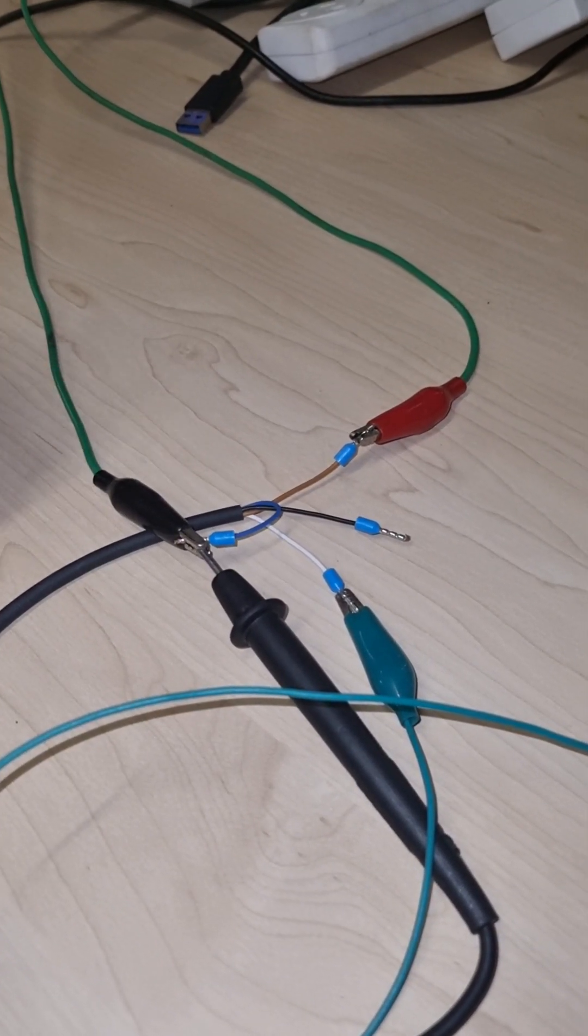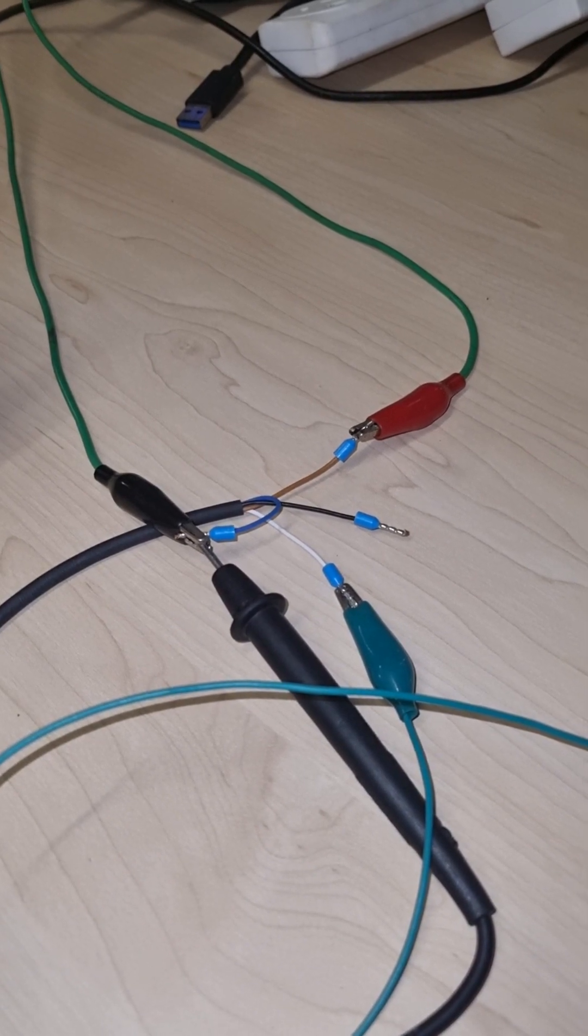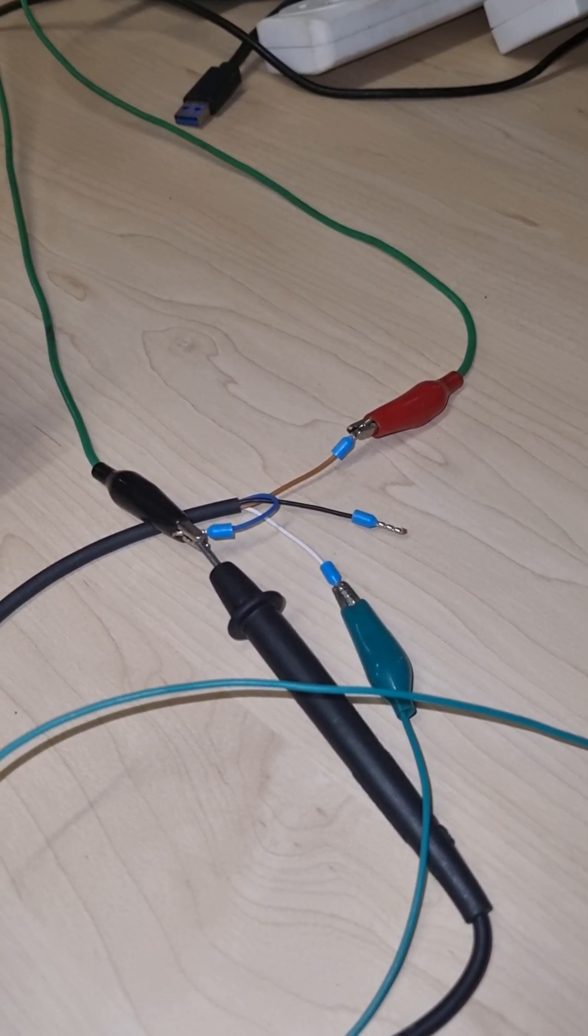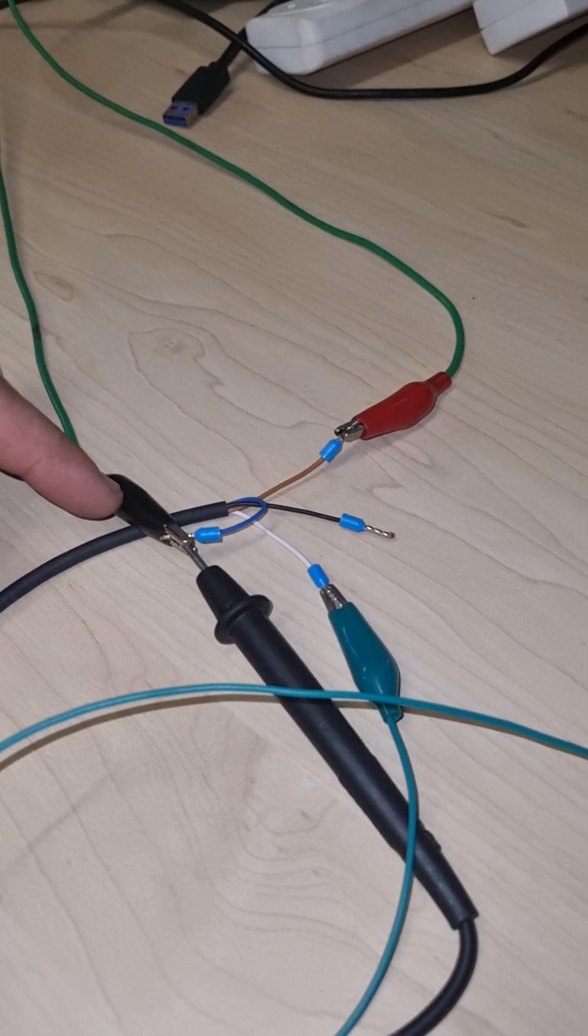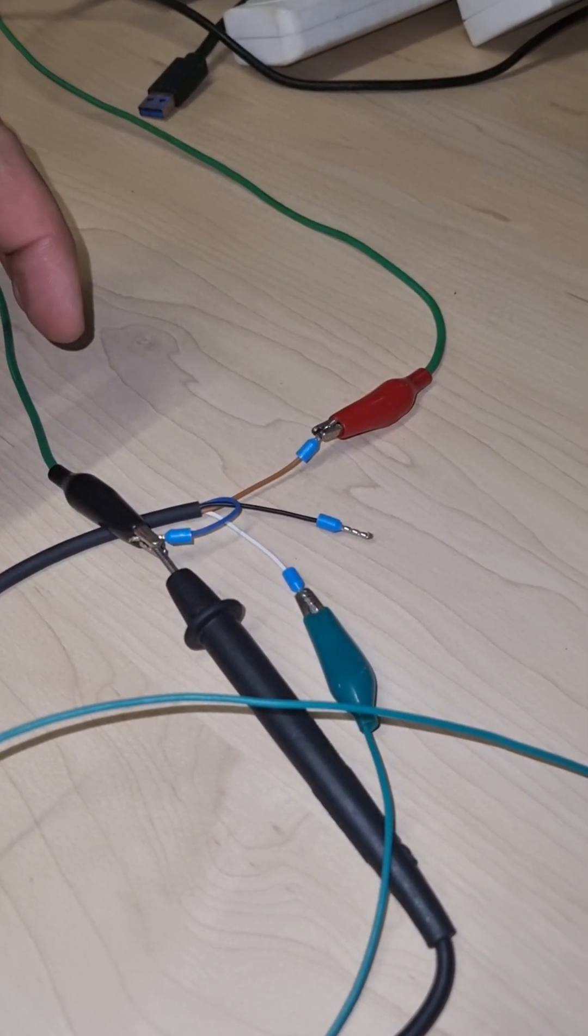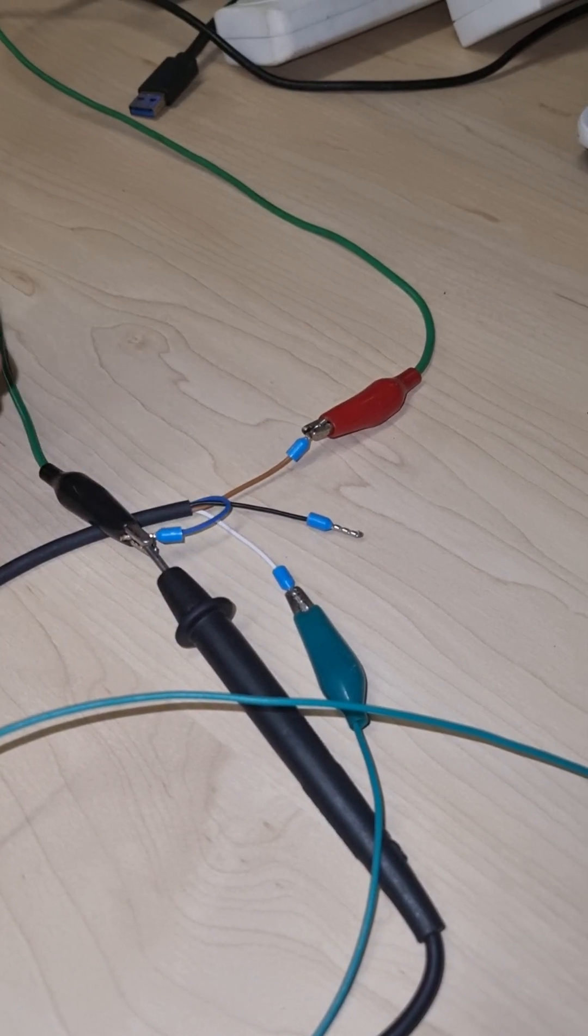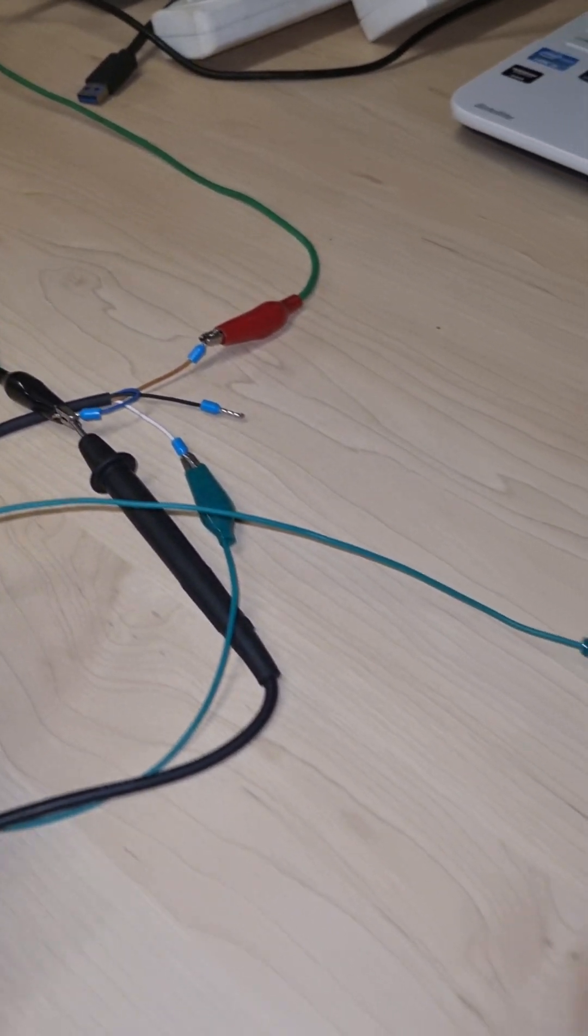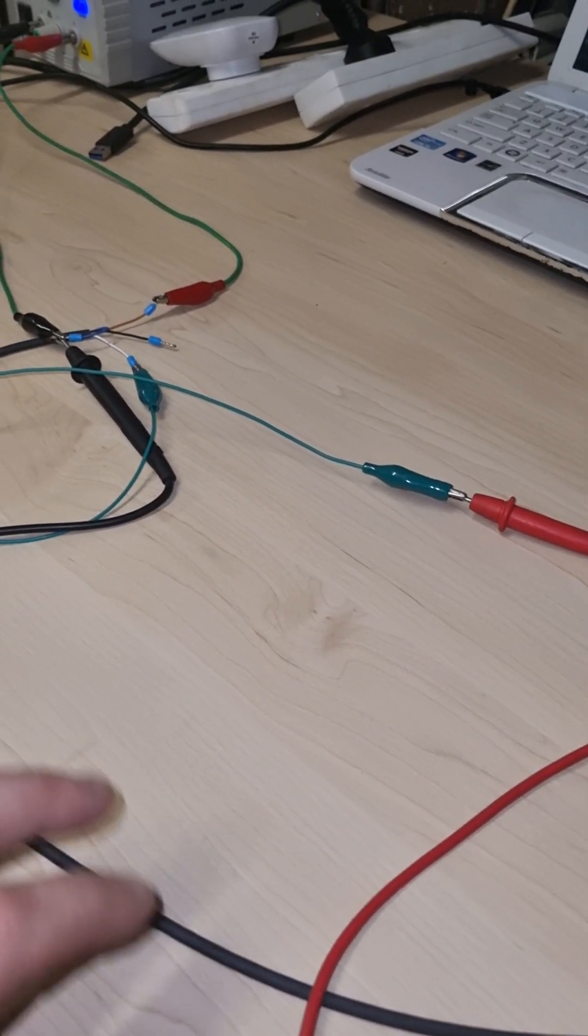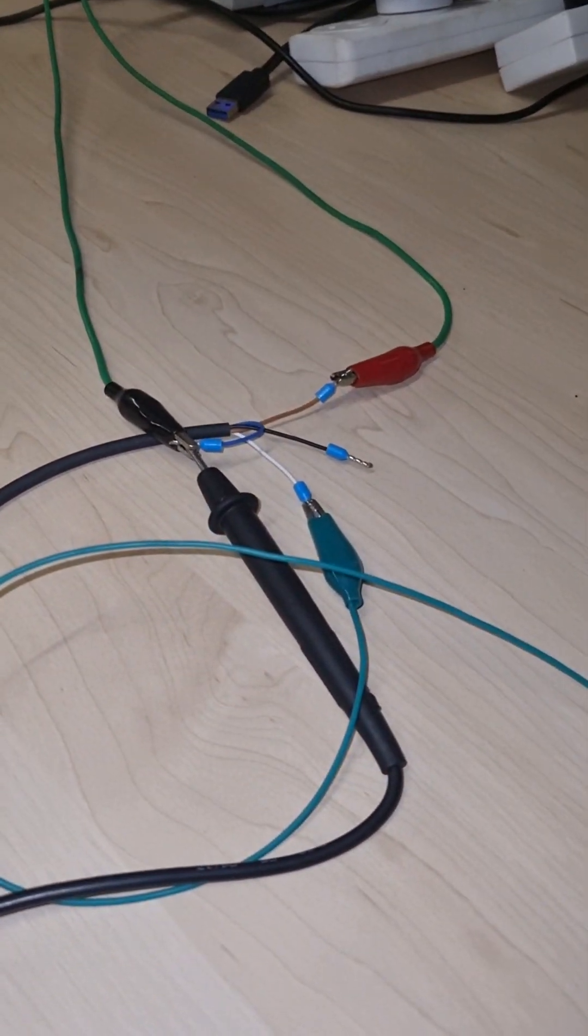Back here wired up for standard digital analog IO, no IO-Link. Grounding the blue wire, positive on the brown wire. White is the analog positive to the multimeter and black probe on the ground.